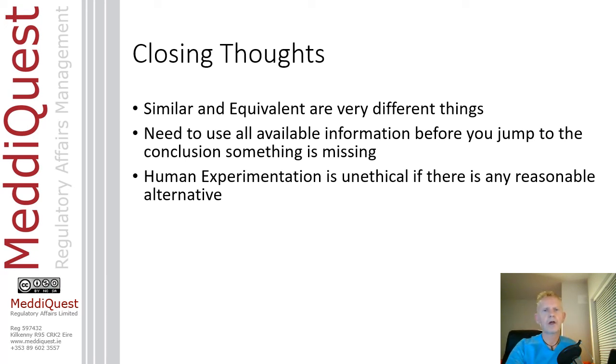No. Human experimentation is generally unethical if there's any reasonable alternative. And if you find your notified body or anybody else starts telling you otherwise, you start throwing the Helsinki declarations back at them. Make sure they can do the ethical justification for you if you disagree with it.